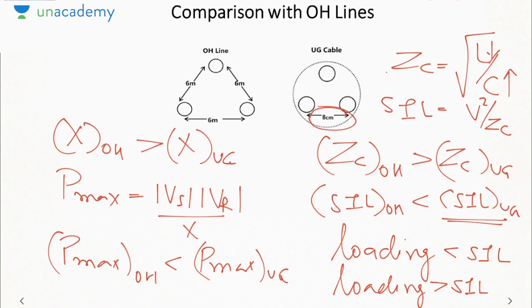And to compensate the Ferranti effect, we can use a series reactor. Why? Because Pmax is already very high in case of UG cable. Even if you use a series reactor, reactance will increase and Pmax will decrease. But already we are operating at a level much below the Pmax. So even if Pmax reduces, we are safely operating much below the Pmax, with loading decided on the basis of thermal limit. So that is why it is safe to increase the reactance.